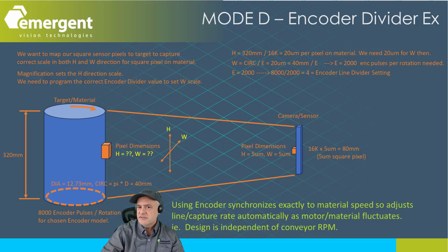A fundamental exercise in line scan systems is to configure the scan rate to create the correct aspect ratio of the pixel. In mode A, which is an all-internal triggering method, we use the line time parameter and simply adjust the line time until the approximately correct height and width aspect ratio is observed. We can calculate this as well, of course. Note that this line time parameter does not track changes in material speed, so the user must take care of this if correct image proportions are desired. In mode D, which is an all-encoder triggering method, we need to set the encoder divider to the appropriate value to correct image proportions. This method is popular since it does track material speed without any runtime adjustments.